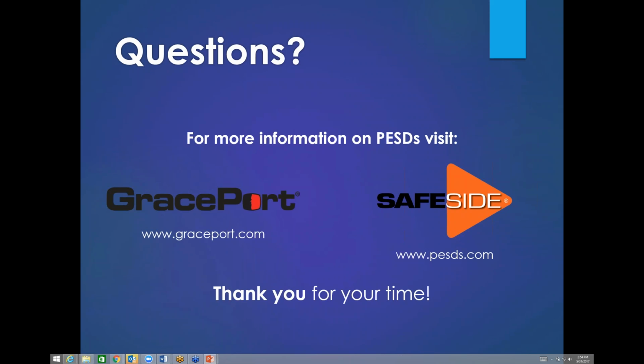Let me have something to say about that one, Dan. Okay. I don't ever want to have a non-electrical person using a proximity tester on exposed parts at 50 volts or more. The proximity tester represents an alternative for a qualified worker to use. You're coming way too close to energized parts if you have an unqualified person using a glow stick or a tick tracer. So the glow stick and all of that is just an alternative for somebody who's properly trained. We never want an unqualified person using a proximity tester on the equipment. And that is, again, one of the benefits of the PESD: you're not in proximity to those tests.